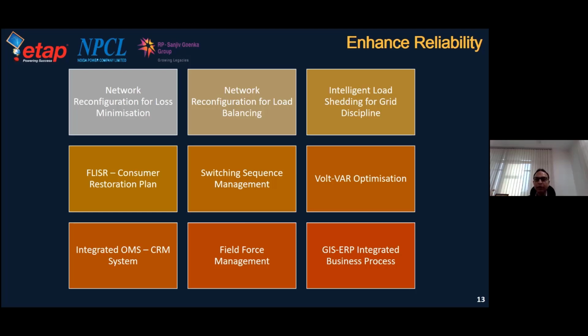Then the volt-VAR optimization is a very beautiful application. It has helped us to do the optimization of our reactive power, because on reactive power drawal also, when the grid frequency is low, every utility is subjected to incurring some cost by virtue of the penalty mechanism prevailing. It has helped us to do the proper optimization of our reactive power, as well as ensure that our tail-end location consumer is getting the proper voltage profile.